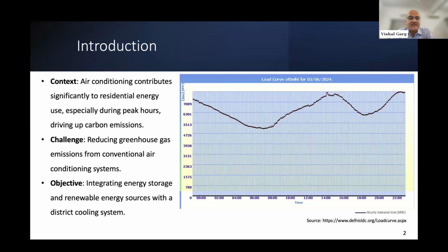I need not spend too much time on this. We already know that the peak nowadays is shifting from daytime to nighttime. Here is a load curve for Delhi, and we can see that the peak is happening in the night. And this is due to the residential air conditioning energy consumption, the AC load, that is leading to this peak. So basically, as already discussed, we can use thermal storage, charge that thermal storage in the daytime when renewables are available, and reduce this nighttime peak, which is coming mostly from regular coal-based, oil-based, or those kinds of energy sources.